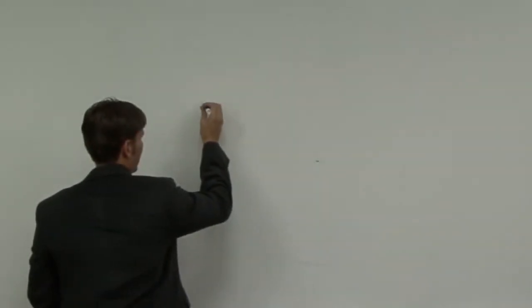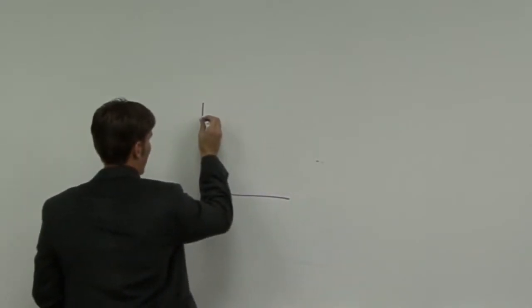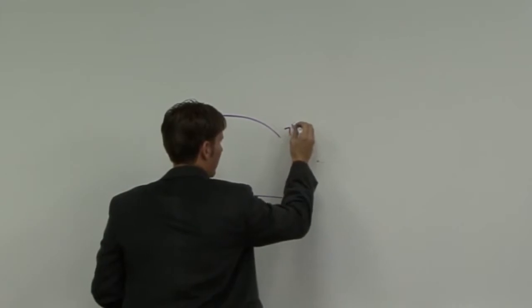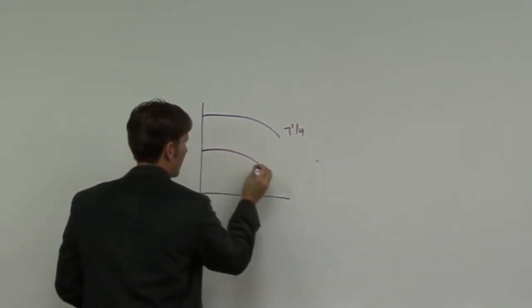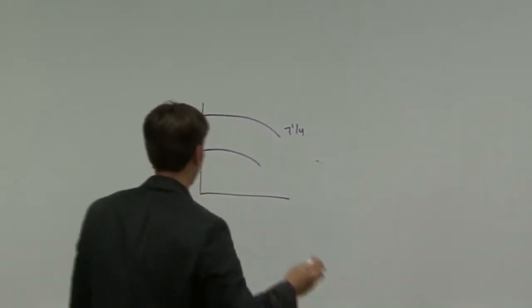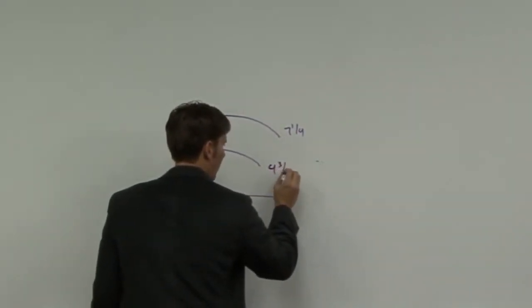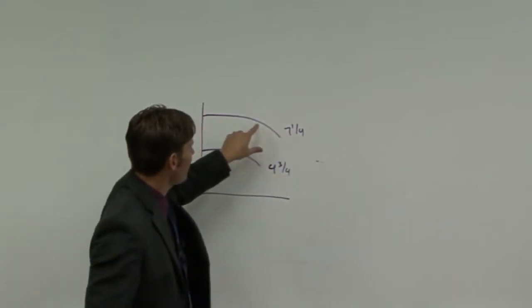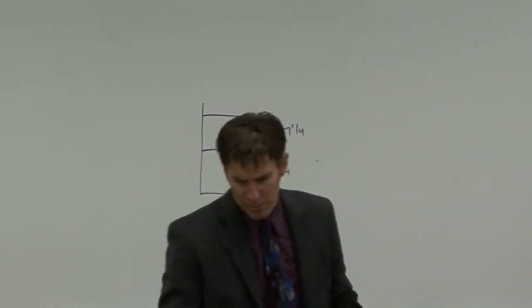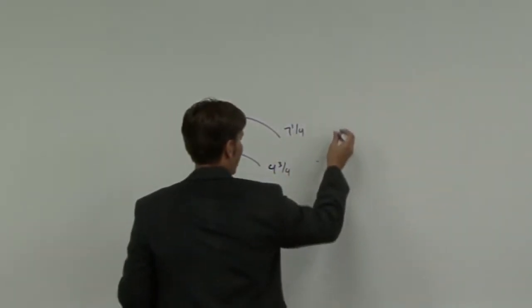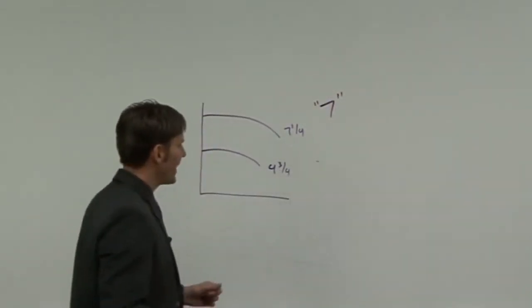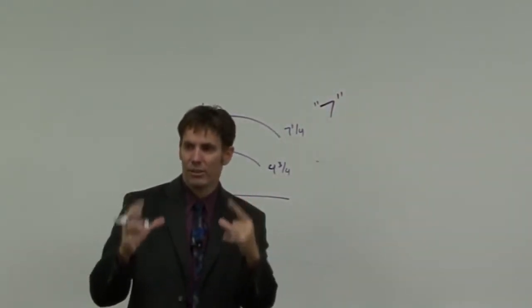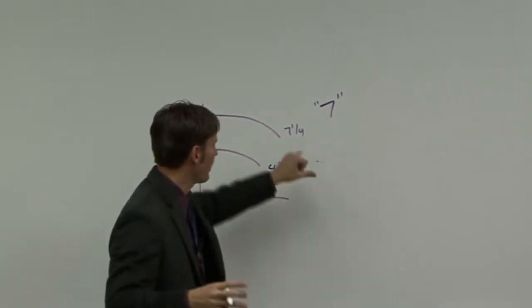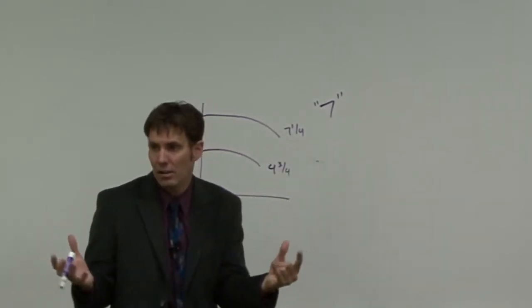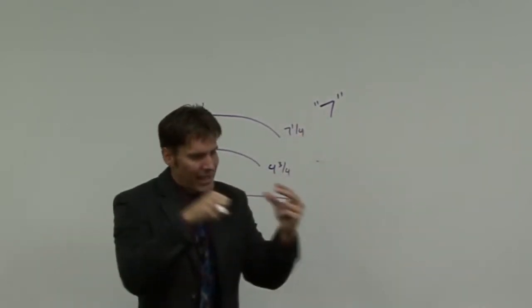If I were to draw a similar pump curve up here on the board, I've got my 7 1/4 down to, what did we have, the 4 3/4? This 7 1/4 is the largest impeller trim that I can have. The pump model is an E2.5J7A. That 7, in the model number, designates the size of that volute. The volute cannot hold anything larger than a 7 1/4 inch can or impeller. If I put anything larger in there, it just won't fit.